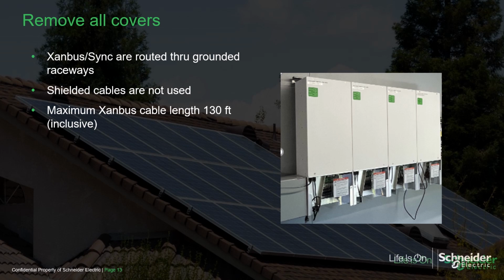Engineering designed grounded raceways into our equipment to keep communication cables isolated from sources of radiated electrical noise. This is because the Xanbus network is an isolated network from chassis ground. As such, there is no metal contact in the RJ45 jack for a shielded cable to make contact with ground. You will note the RJ45 jacks are all plastic. Make sure the total inclusive length of all the Xanbus cables in the network does not exceed 130 feet.